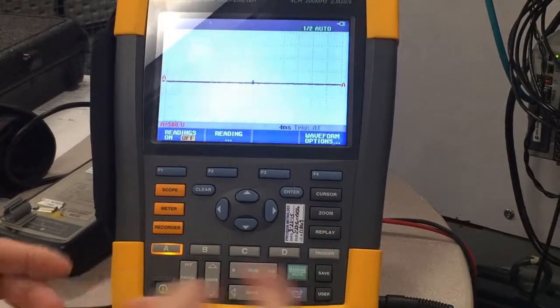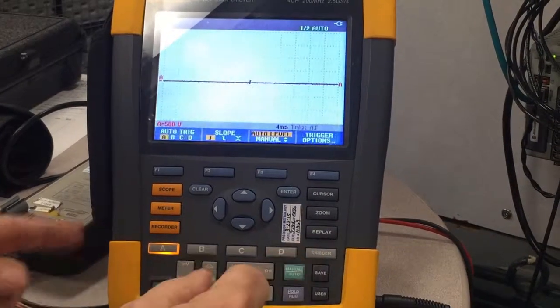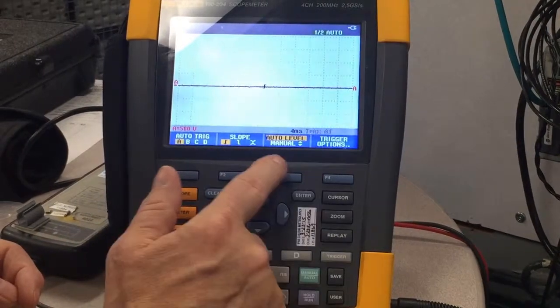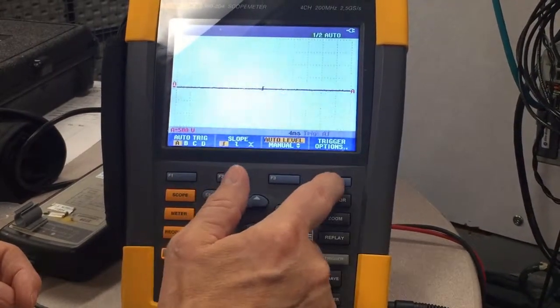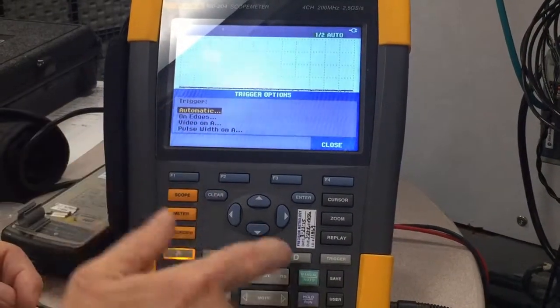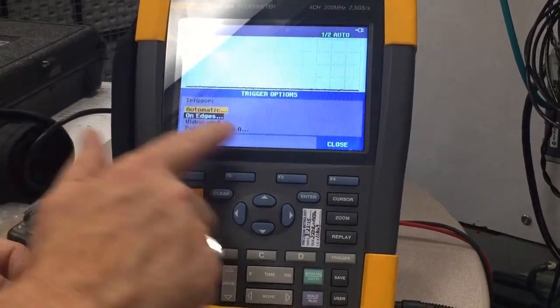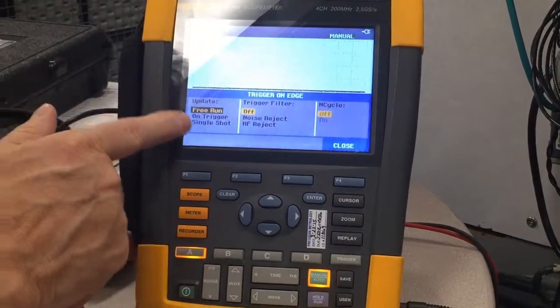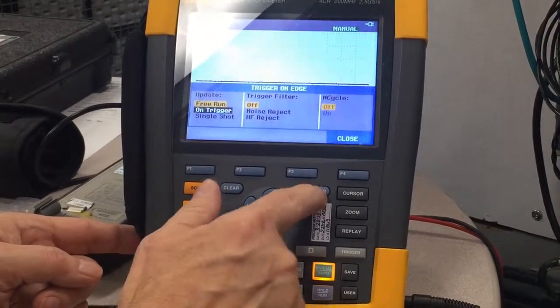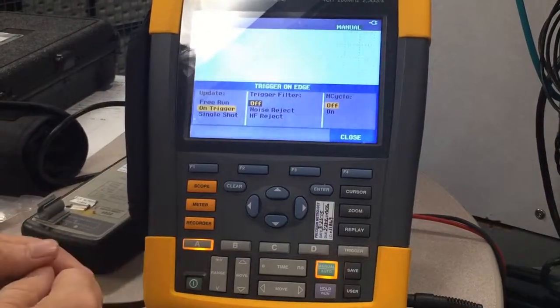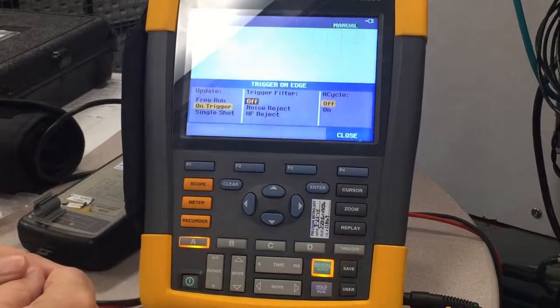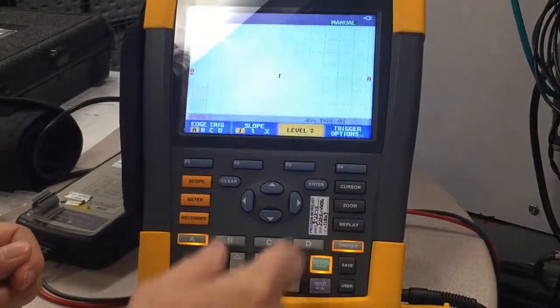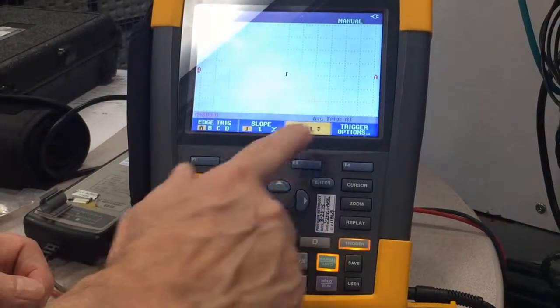The next thing we're going to do is set up our trigger. So, you press the Trigger button. And we're going to make sure we trigger on A. Make sure the slope is positive. And then we're going to look at trigger options. What we want to do is only trigger on edges. So, we scroll down to on edges. Press Enter. And it gives us a new menu. And we want to update only on the trigger. So, we down and then press Enter. So, now we have our trigger options all set. And we're ready to start the drive to take some measurements. We close this out. Close this out. And we'll leave it at the trigger menu right here.